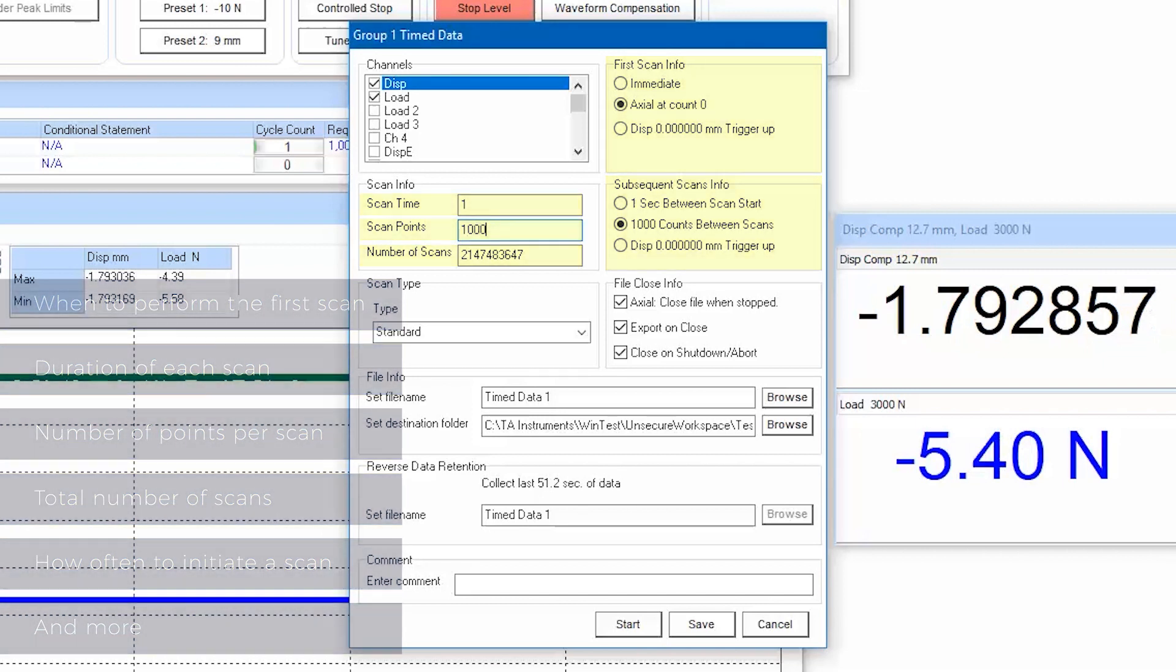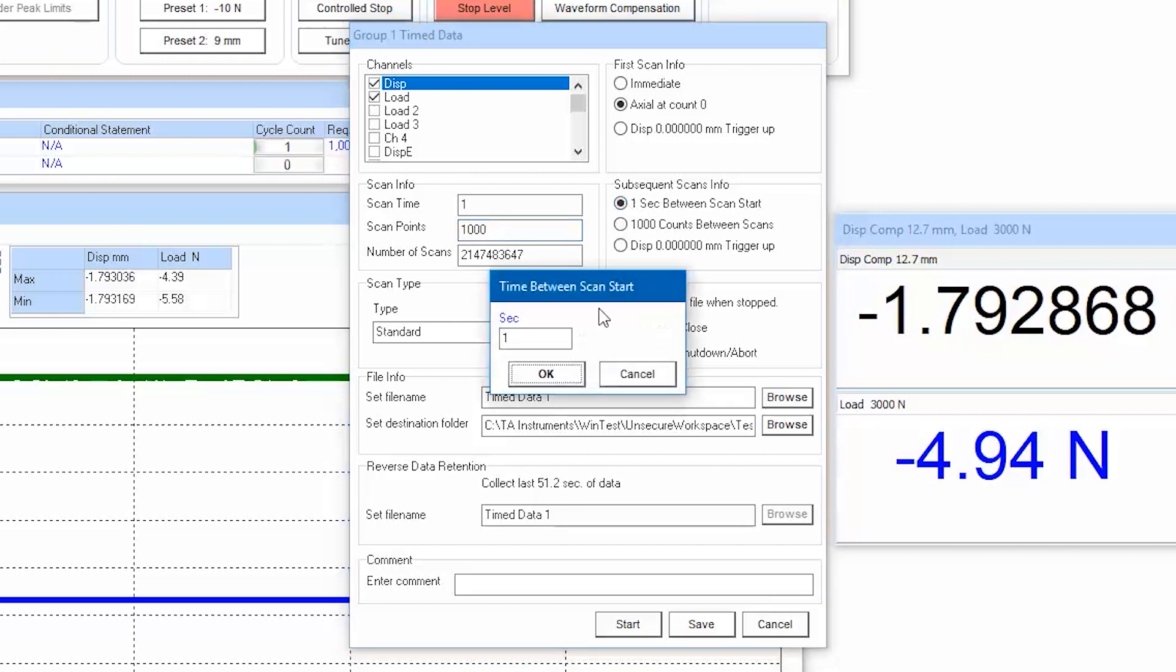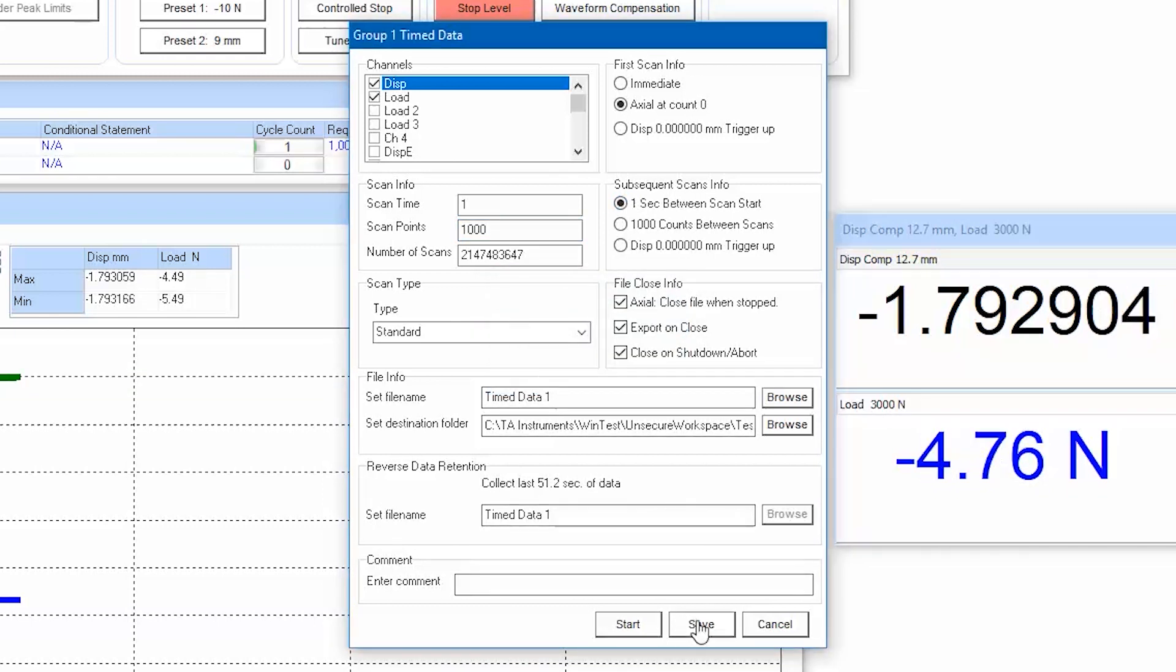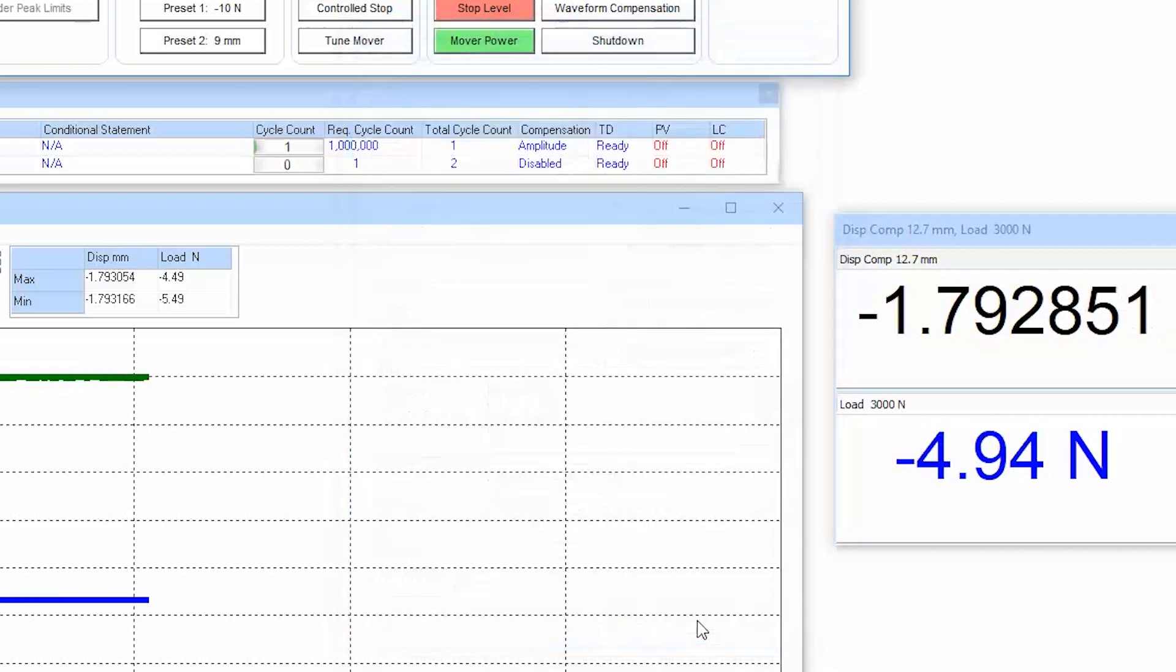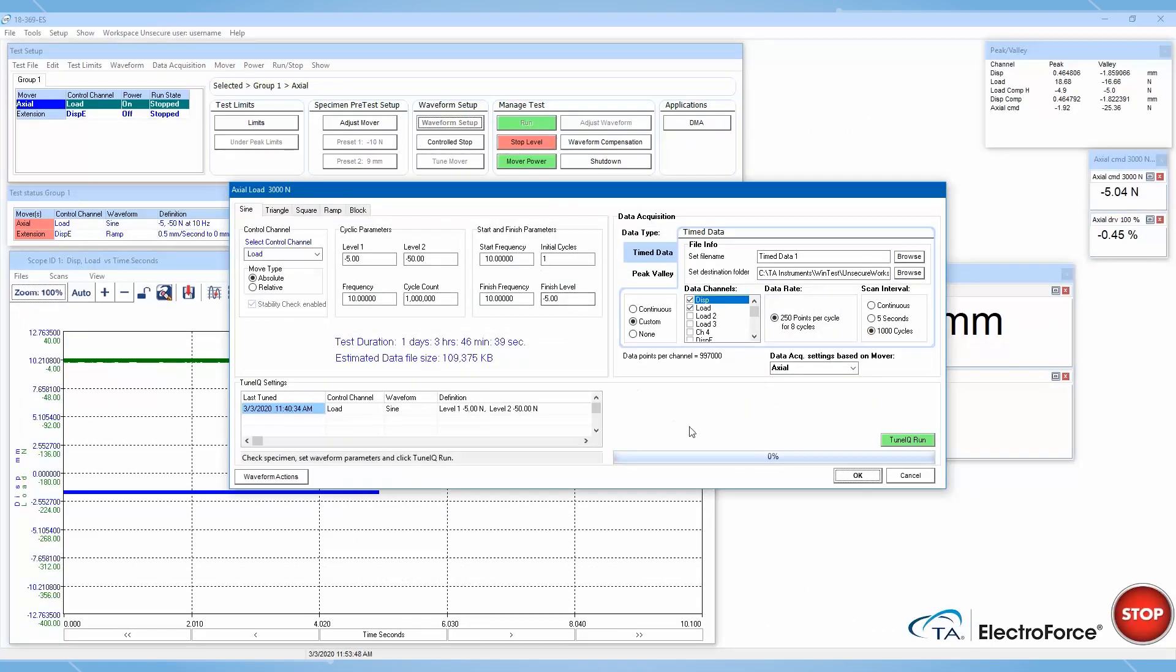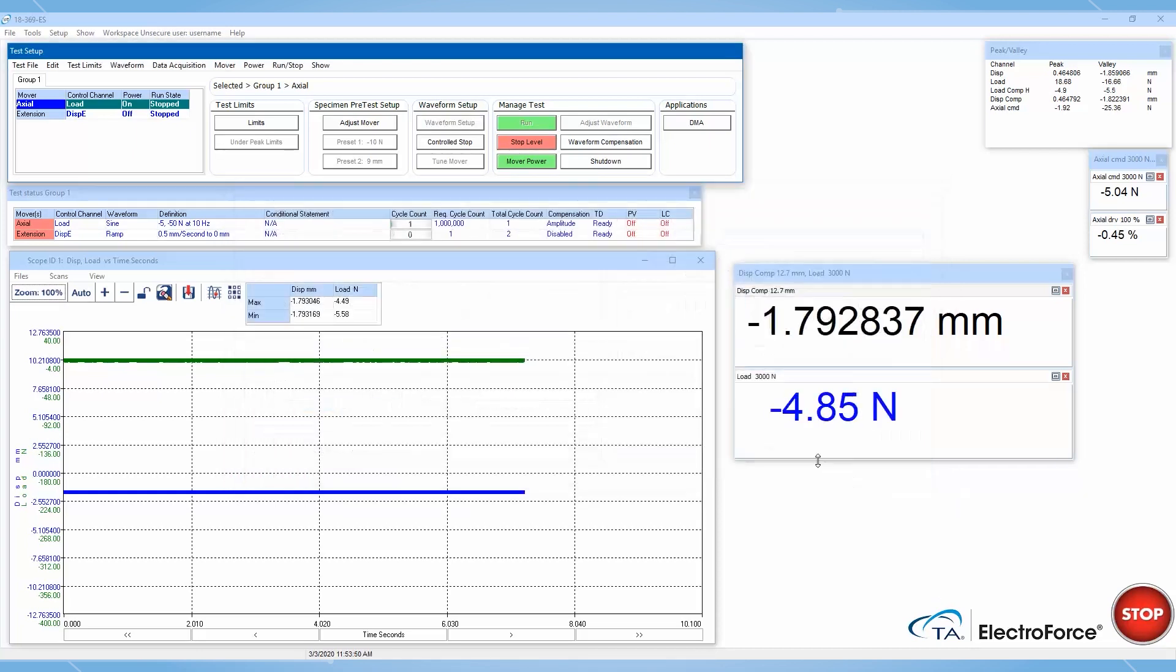In this example with a one second scan time, in order to collect data continuously, I need to set a one second between scan start. Note that the settings on this window are populated by the settings inside of the waveform setup window. If you modify this window and then reopen the waveform setup window, these settings will be overwritten as soon as you exit the waveform setup window, even if you click cancel.